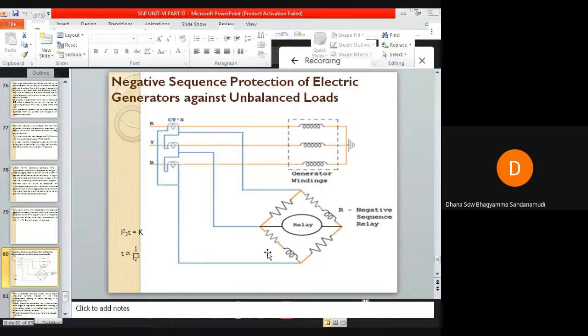If the three-phase stator winding currents are unbalanced, then it is observed that double frequency currents will be induced in the rotor. Consequently, the rotor will get heated up and it will get damaged. Due to the unbalanced three-phase stator, double frequency currents are induced in the rotor, and hence the rotor gets heated up and gets damaged.